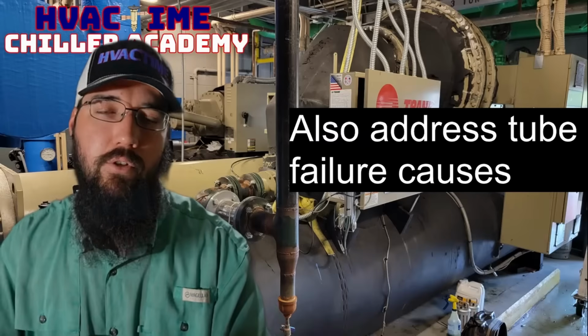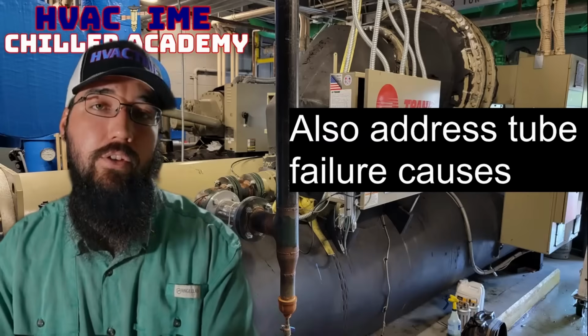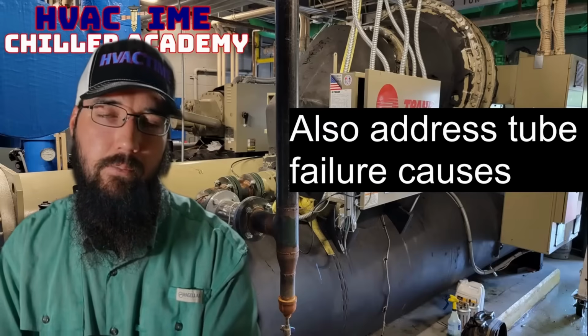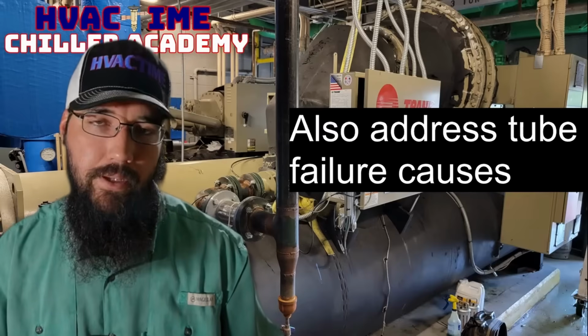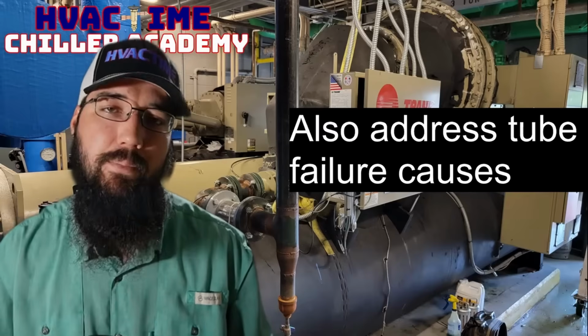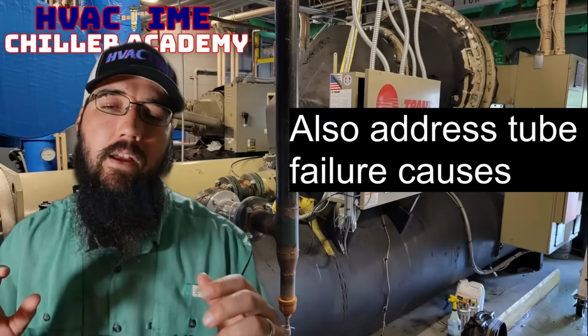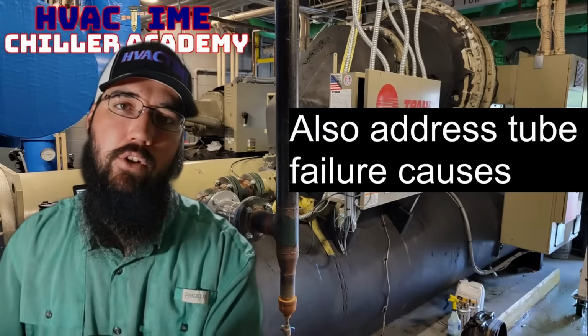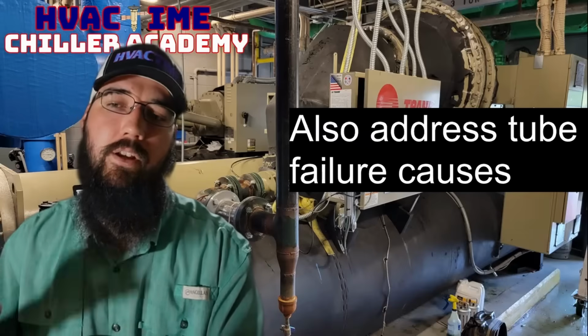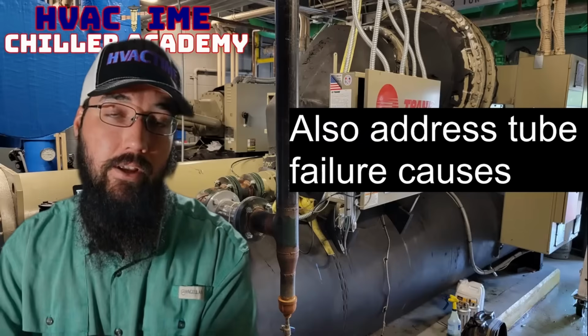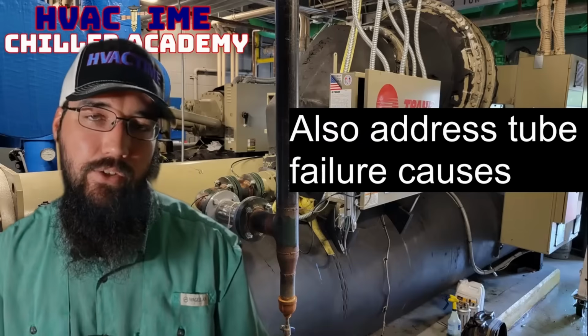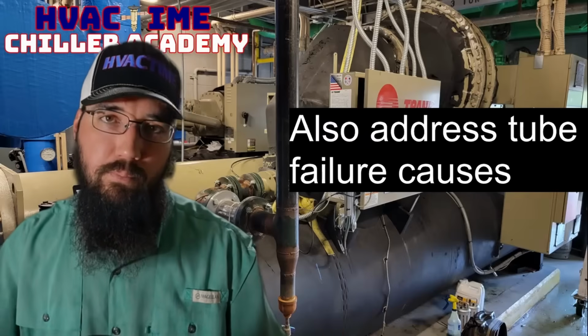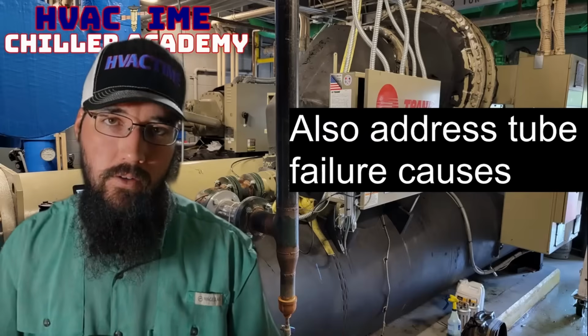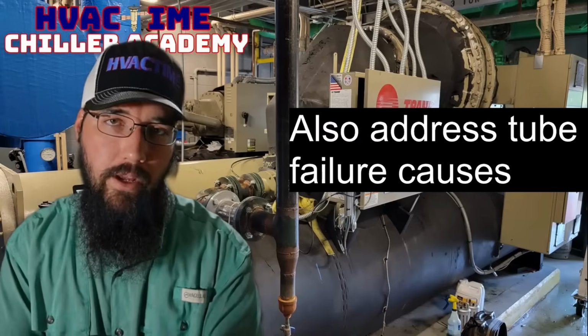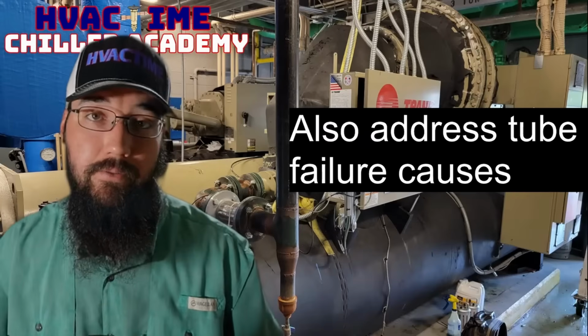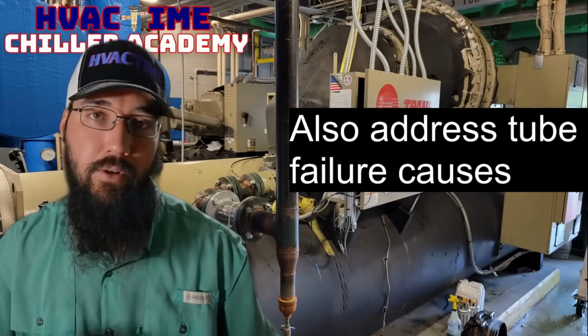So general erosion is one of the methods, and more than just contaminants in the water system, also high GPM. If you're flowing excessive GPM through your heat exchanger, then that extra water flow is going to add additional erosion, because it's flowing through there far faster and harder than it technically needs to. And that puts more wear on your tube wall. Erosion is one way. Just straight debris causing a puncture is another.